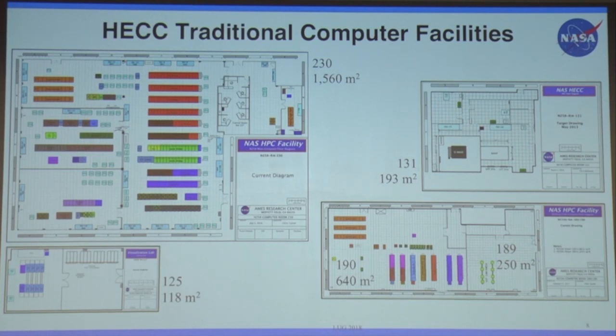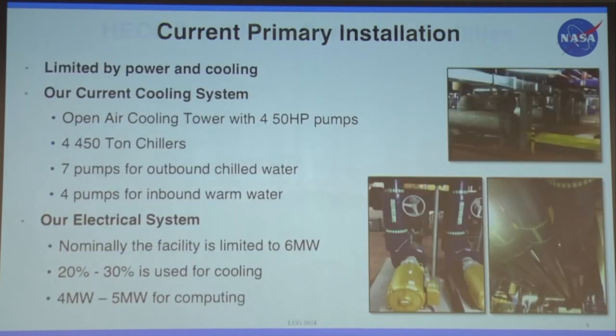Traditional computer facility space, these are our computer floors where things sit, and it's largely up to this point been classic water towers with chillers that you run. We get PUE ranging from 1.5 on our oldest systems to about 1.3 on the main floor where Pleiades is, and that's not bad for that style of system, but it's still pretty high.